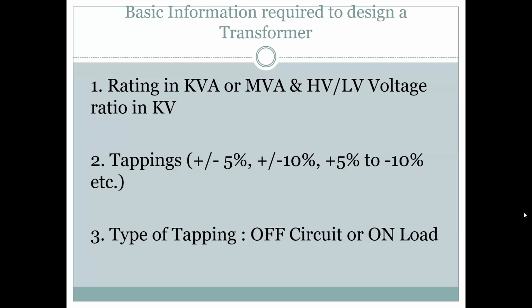What is the inductive load? What is the capacitive load? The transformer rating is decided based on these things by the consultant, the project manager, or the users. They give us the rating. Sometimes I tell them we are not the project designers. You have to tell us what you want, or if you want us to decide the number, then you have to make us the project consultant. You only know your voltage. We don't know whether you are getting supply from 33 kV, 132 kV or 220 kV. At minimum we need all these details.